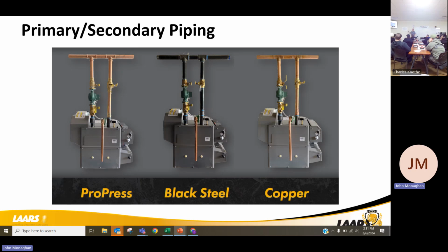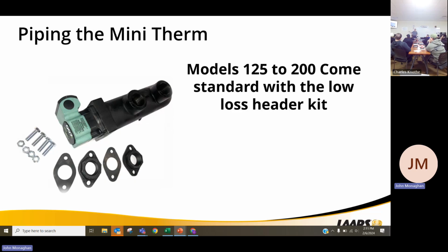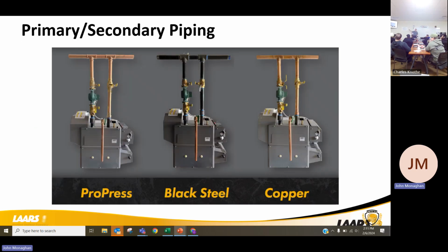Talk about that. So, primary, secondary piping. If you don't want to use that kit, and you want to do your primary, secondary piping, there goes your primary, secondary piping at its easiest. Pro pressing your 2 T's together, doing black iron pipe, doing copper is going to do your primary, secondary for you. Not saying it's needed on all of the products. The 150 and up, 125 and up, say it's almost non-negotiable standard. Your smaller products, for the most part, the systems they're going into, primary, secondary is not required.